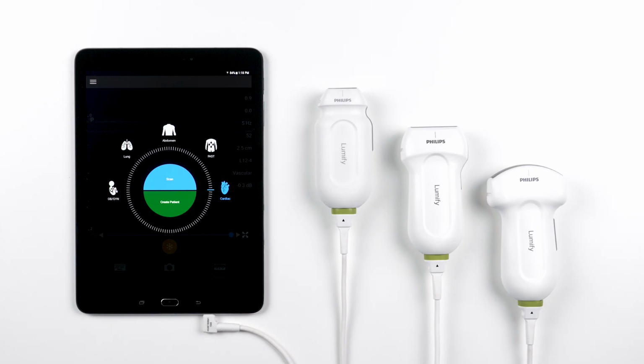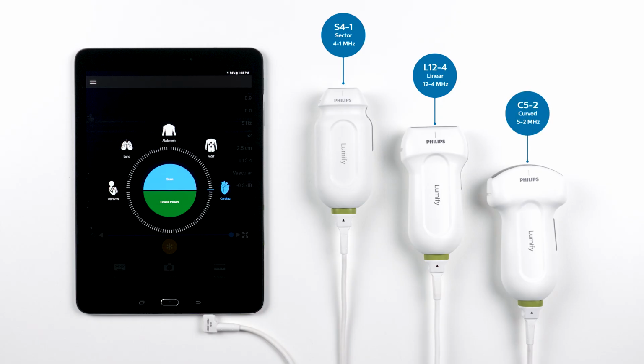The letter at the beginning of the name tells you the type of transducer it is, and the numbers tell you the frequency range it uses. So the S4-1 is a sector transducer and the frequency range is 4 to 1 MHz. The L12-4 is a linear transducer and the frequency range is 12 to 4 MHz. The C5-2 is a curved array transducer and the frequency range is 5 to 2 MHz.